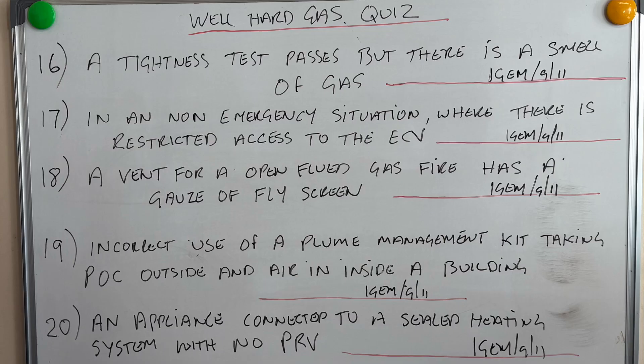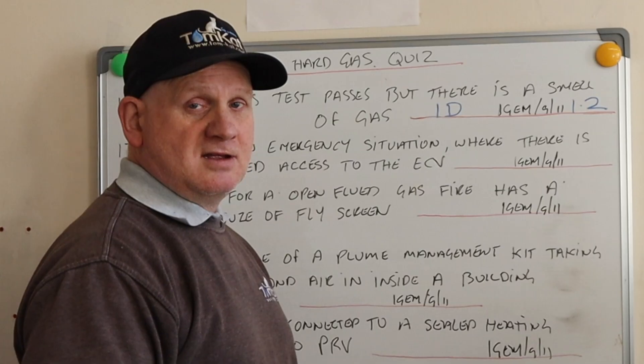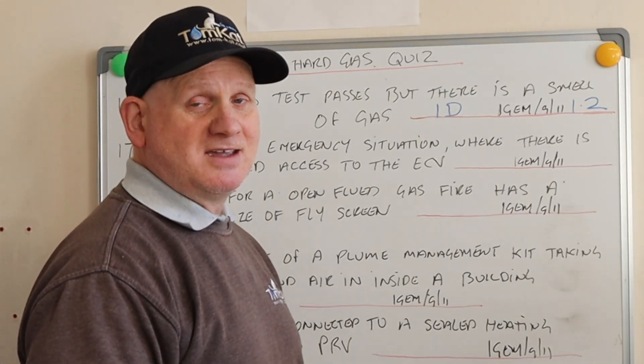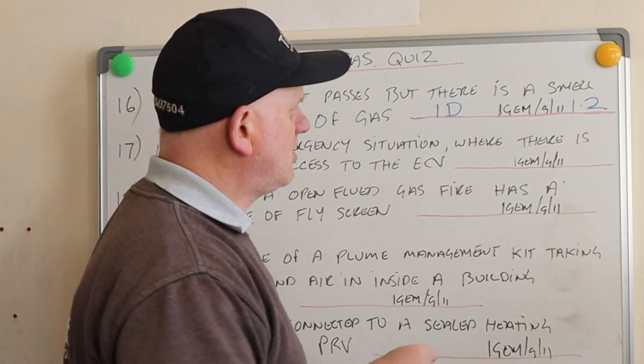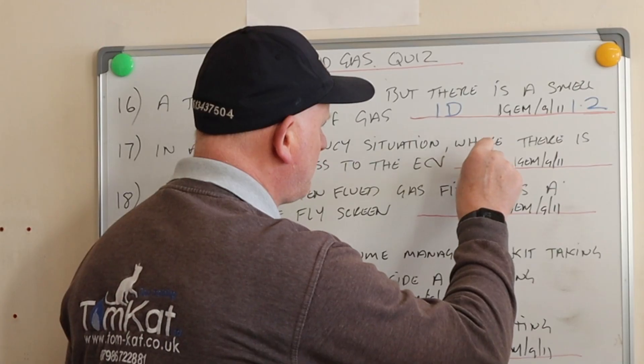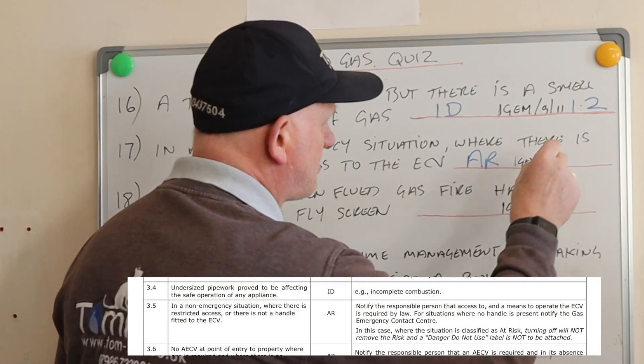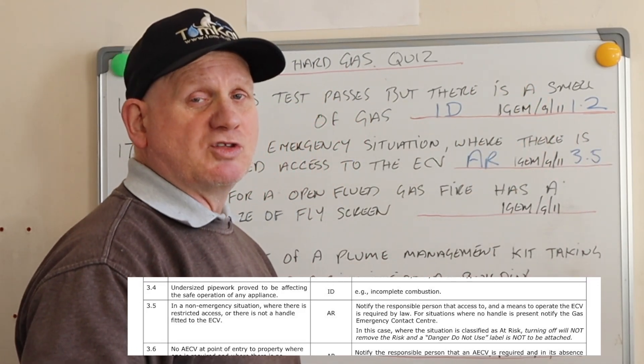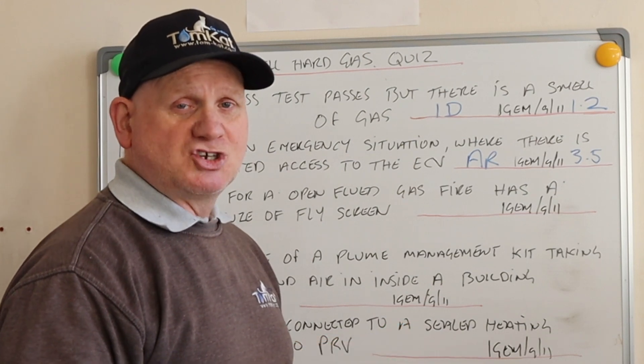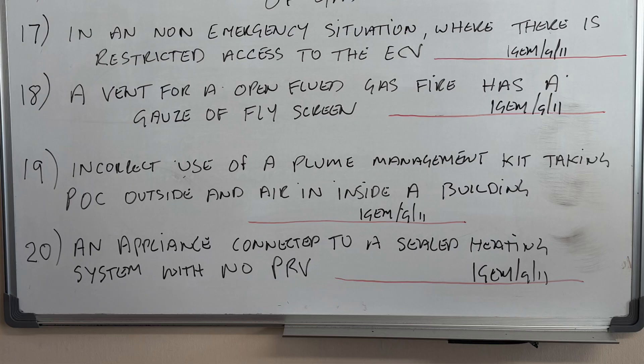Question seventeen: in a non-emergency situation where there is restricted access to the ECV. If you said ID, you'd be wrong — it's actually 'at risk,' and if you want to know where it is, it's at section 3.5 of the IGEM G11 unsafe situations procedure.